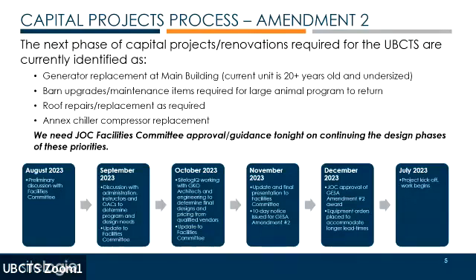Can you get us the cost both ways? Sure, since you didn't calculate additional load, you could put all the new load on a new gen set, completely separated, on a pad out back. But that messes with your permits and everything, and would probably well exceed the cost differential, since you'd need separate main power feeds all the way out back. We'll run the numbers for it.